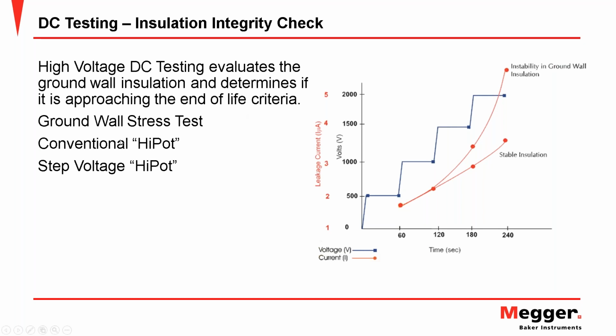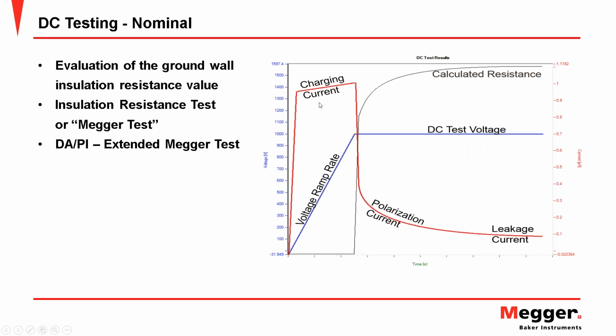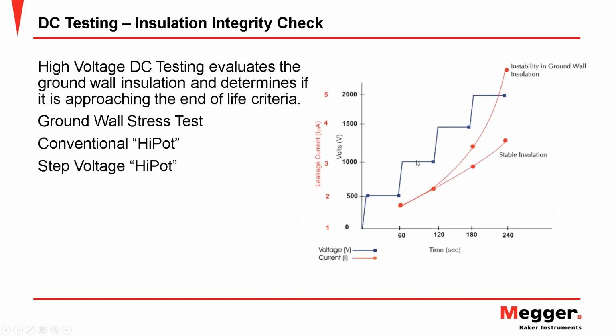And one of the ways we do that is through, of course, the conventional HiPot, which is very similar to the test I just showed in the previous slide, except that the test voltage now is at least 2 times line voltage plus 1,000 volts. At a minimum, that would be, say, like a field testing requirement, maybe even higher for quality testing. But as far as the test is concerned, it's exactly the same test, just done at a higher voltage relative to the nominal nameplate value.